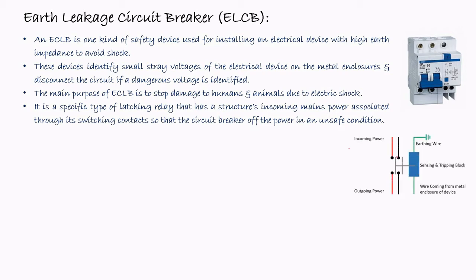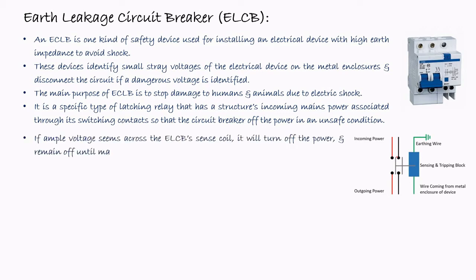So here the circuit is shown with the ELCB. This is the incoming power, this is the outgoing power. In between, the ELCB is connected. If there is any abnormal condition sensed by the relay of the ELCB, then this circuit breaker will trip the main circuit, so the power transmission will be stopped. If ample voltage streams across the ELCB sense coil, it will turn off the power and remain off until it is manually reset. So remember one thing, when the ELCB trips, it should be manually restored.